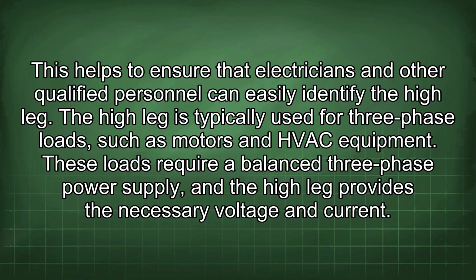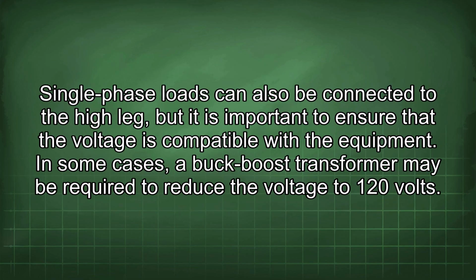The high leg is typically used for three-phase loads, such as motors and HVAC equipment. These loads require a balanced three-phase power supply, and the high leg provides the necessary voltage and current. Single-phase loads can also be connected to the high leg, but it is important to ensure that the voltage is compatible with the equipment. In some cases, a buck-boost transformer may be required to reduce the voltage to 120 volts.